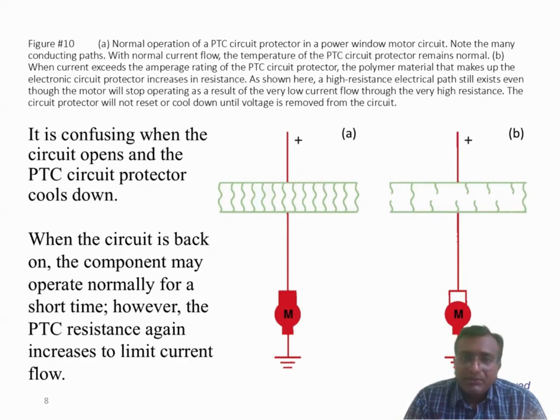When the current flow is normal, the temperature of the PTC circuit remains normal. But when the current exceeds the amperage rating of a PTC circuit protector, the polymer material which makes up the electronic circuit protection increases its resistance. So due to the high resistance electrical path, the current flow to the motor will slow down, and through this high resistance, the circuit will be protected.